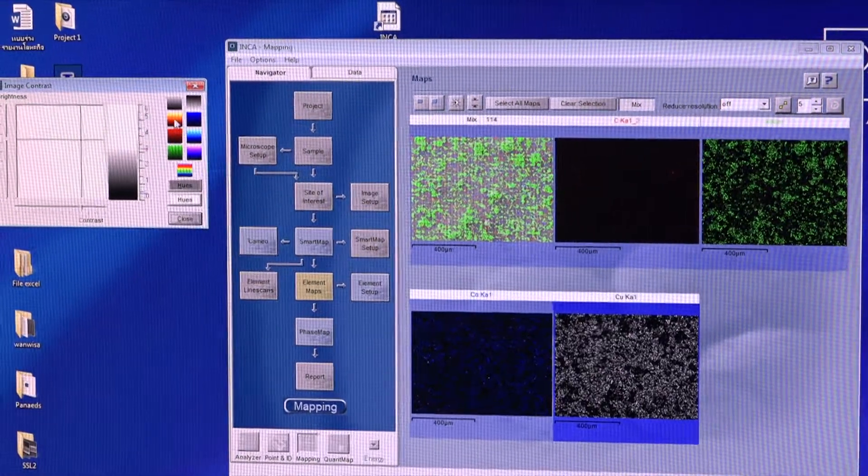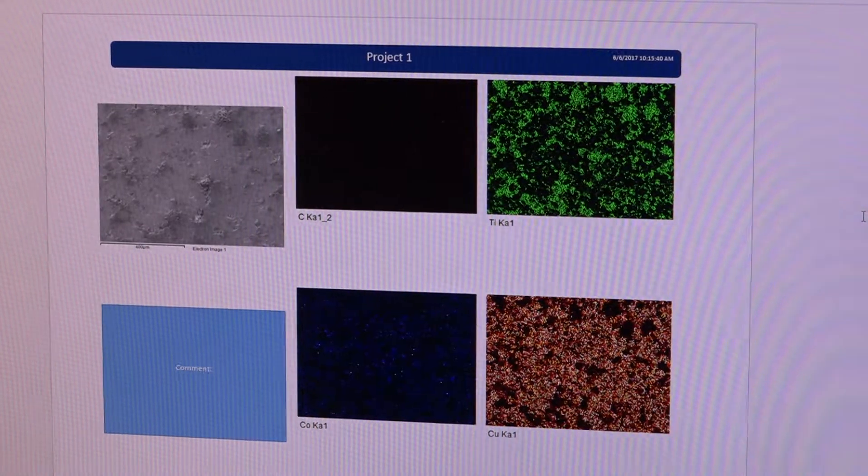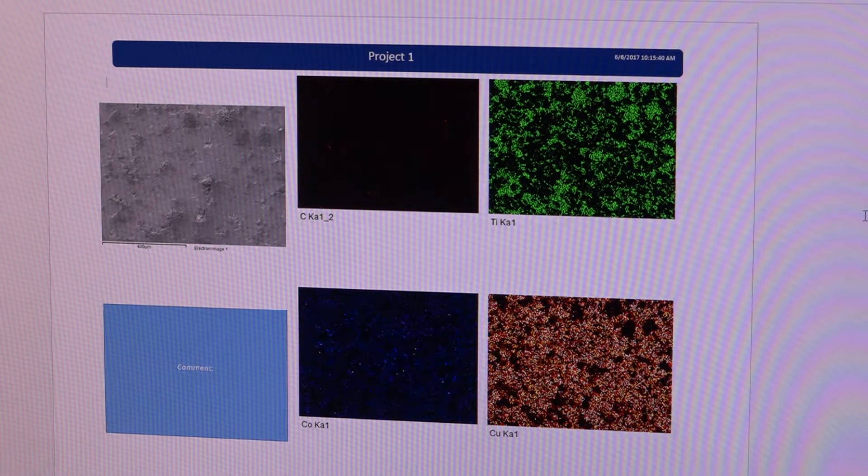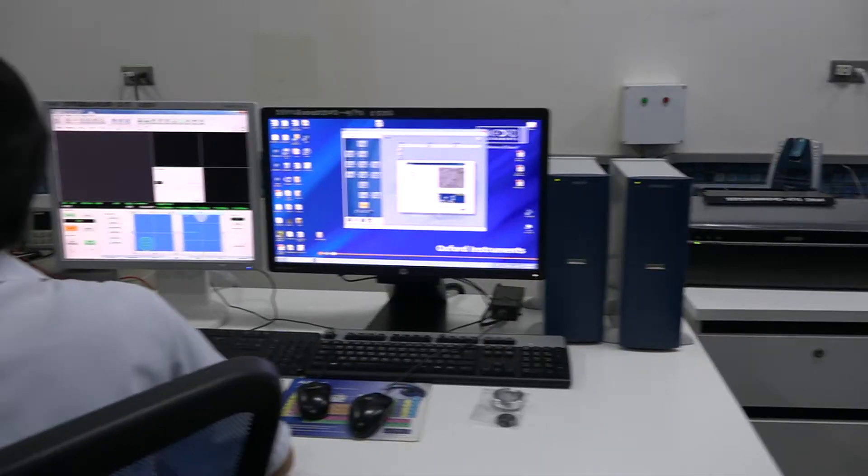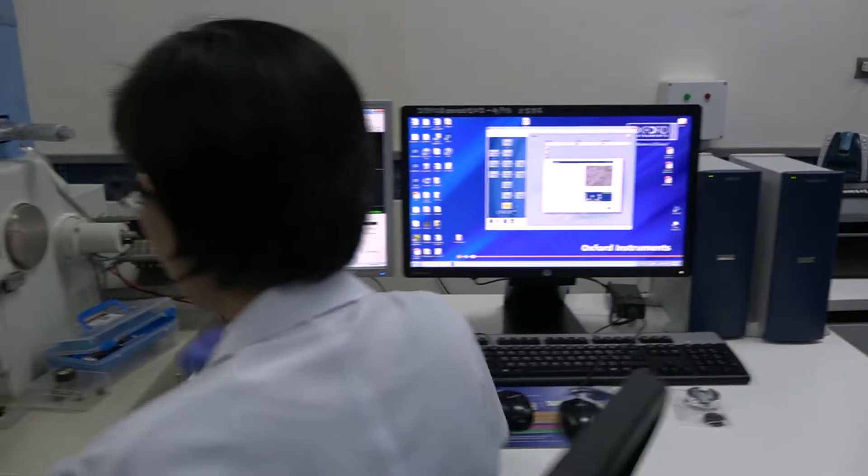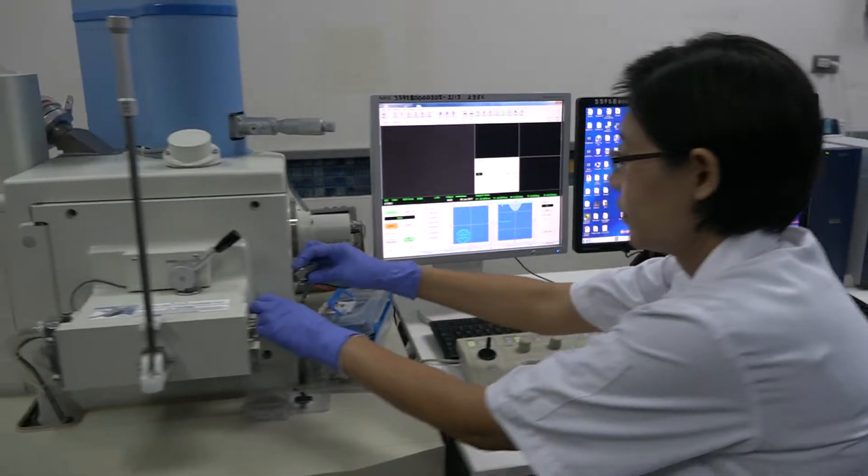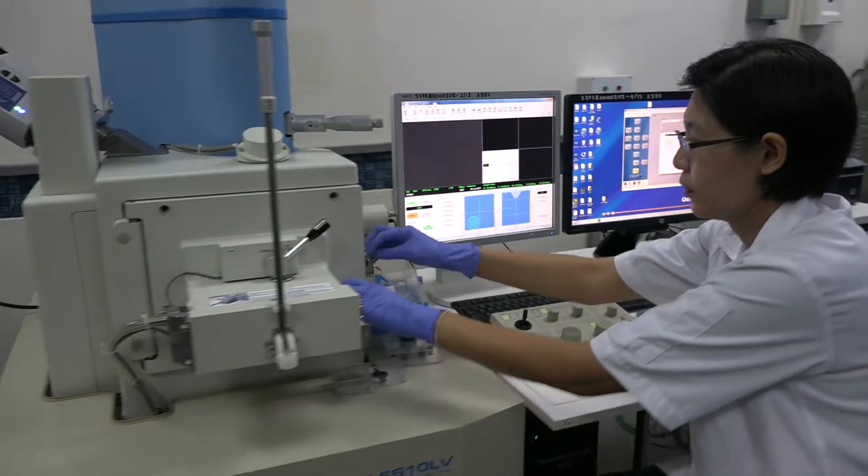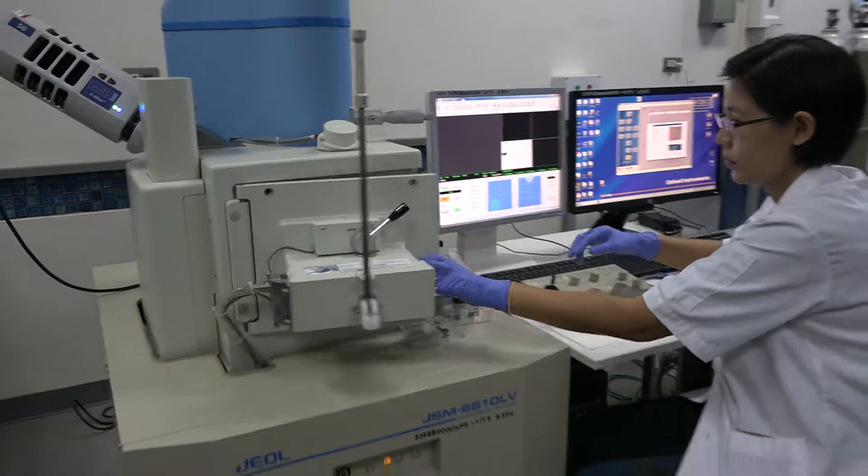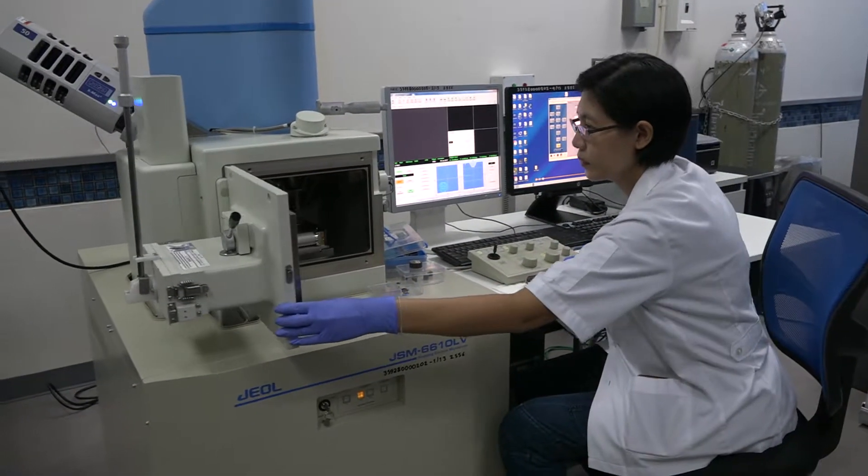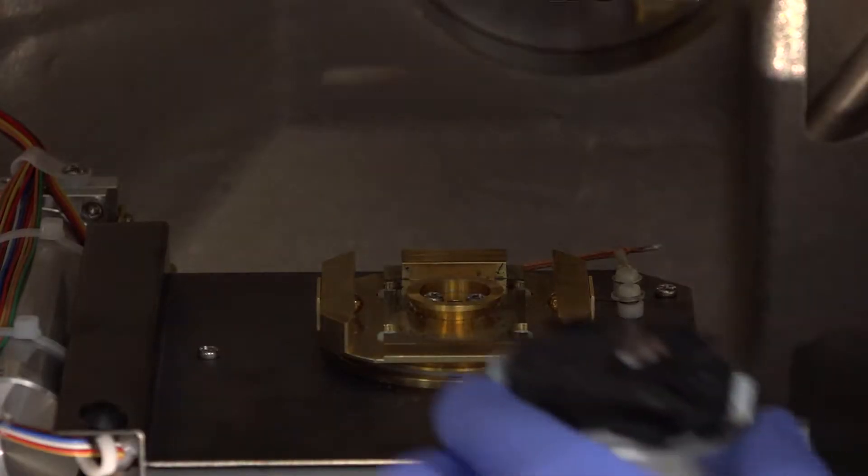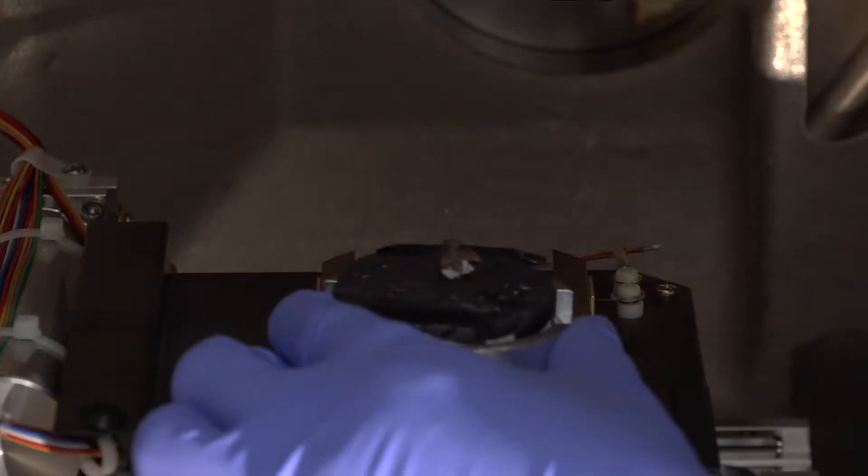EDS limitations: no detection of elements below boron, X-ray detection limit 1000 to 2000 ppm or 0.1 to 0.3% by weight depending on the element, and samples must not contain fluids.